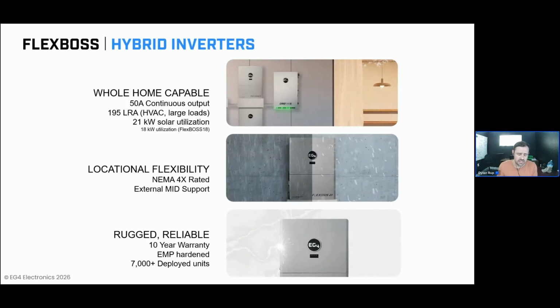Not only is it rugged in the context of its deployment location, but the power capability of the system is rugged as well. The unit comes with a 10-year standard warranty, and we're able to really rely on significantly more than 10 years of performance out of these units due to the high quality power electronics that we're using, to the point that this unit is not only capable of withstanding the typical surges that you might see from the utility grid at any given point in time, but even more extreme surges, those that can be caused by things like electromagnetic pulses.